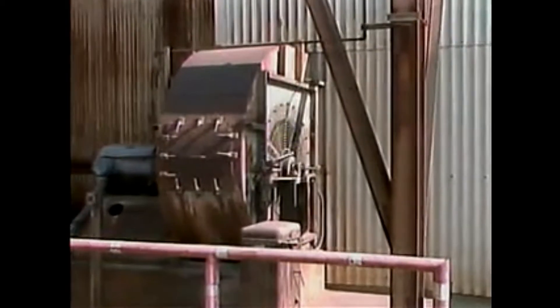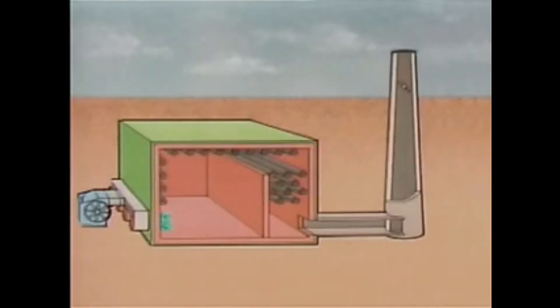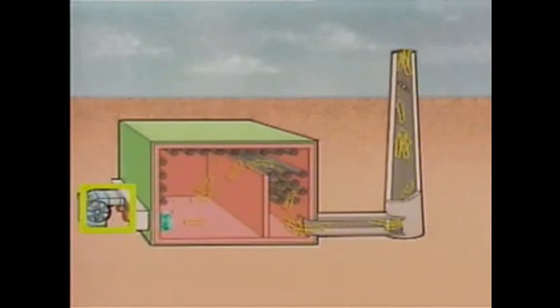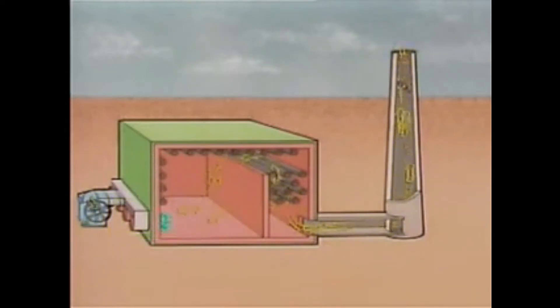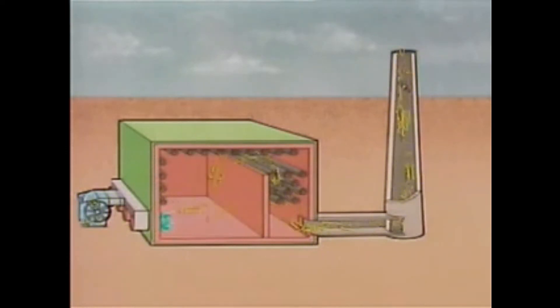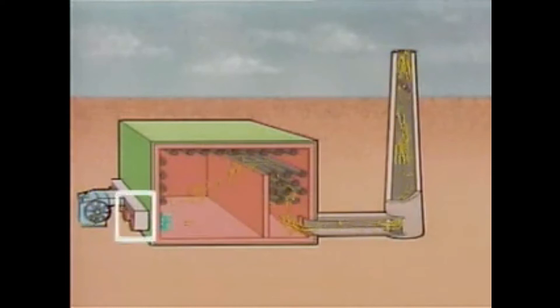Air and combustion gases are moved through force draft furnaces by fans. In a force draft furnace, a fan called a force draft fan draws air from the atmosphere and forces it into the furnace. The burners are mounted along one wall, and the combustion gases flow through the furnace and then out through the stack. Airflow is controlled by coordinating the positions and operation of the stack damper, the burner registers, and the fan.